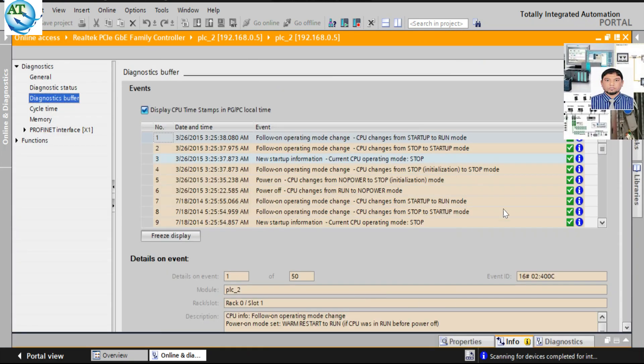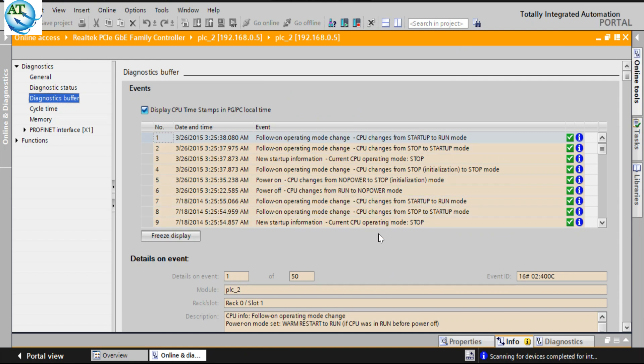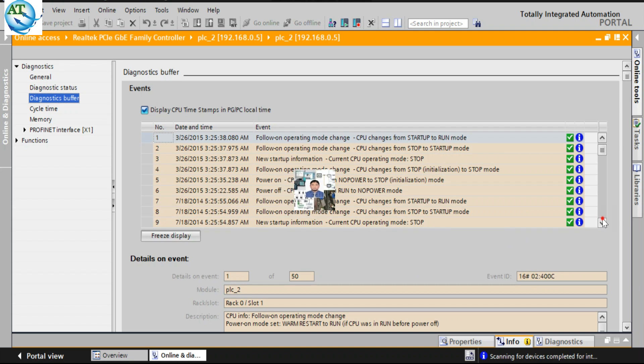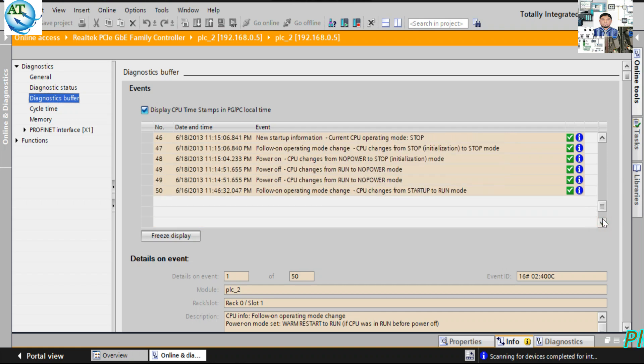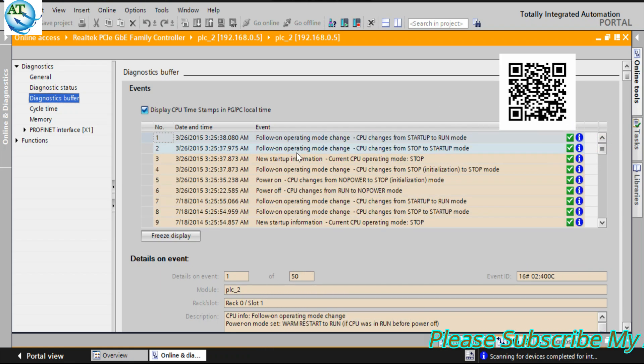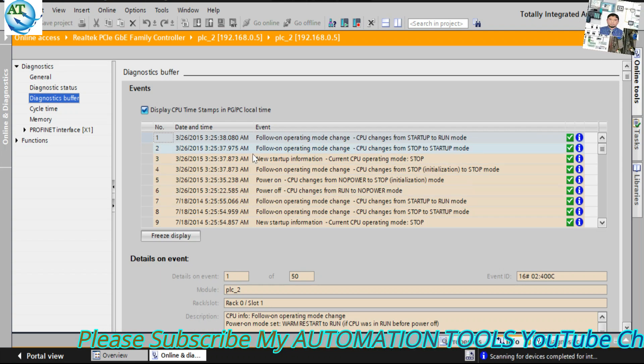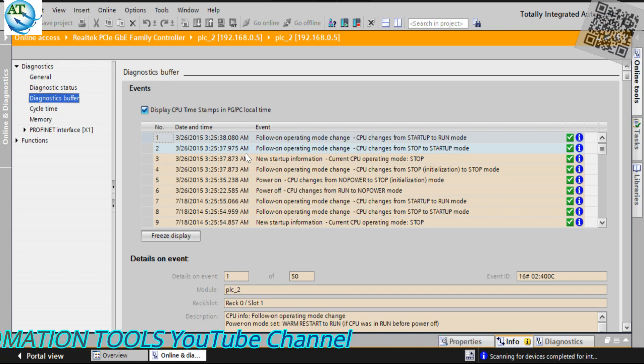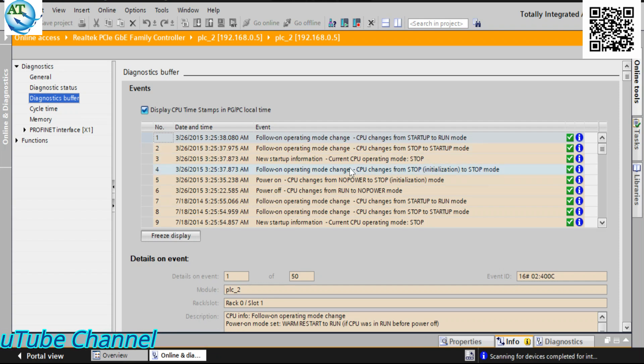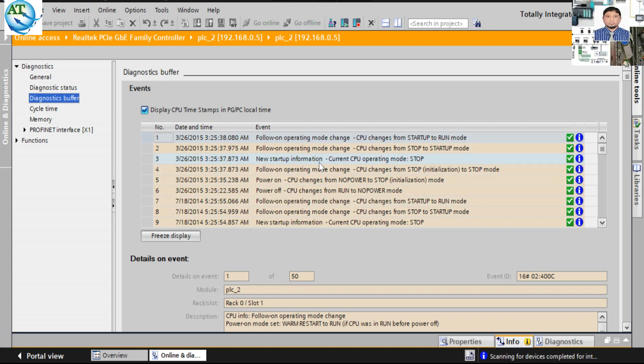Then go to the Diagnostic Buffer — this is the most important section. It is the Diagnostic Buffer, also called Event Memory. In other CPUs such as the S7-300 or S7-400, you find Event Memory. Here you see the Diagnostic Buffer. In the Diagnostic Buffer you can see the Event Memory with dates. You can see all the information — all the events and everything you have done in this CPU, step by step, with date and time. You can find this in the Diagnostic Buffer and use it to identify faults.